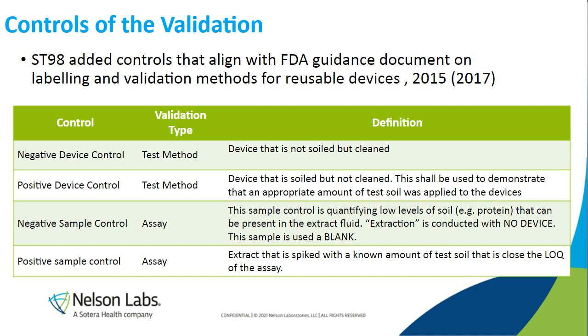Now, positive sample control is a new control that's been there, but not relatively discussed openly. And this control is one that is assessing the test soil that you're using. As you know, if you're not aware, for cleaning validations, we're using simulated use test soils. Now, these test soils can be purchased or can be prepared in-house. And when you prepare in-house, you have to do some qualifications, to make sure that if you're testing your end product with protein or hemoglobin or TOC, whatever you are assessing can be picked up by the assay that you're performing for your end result.